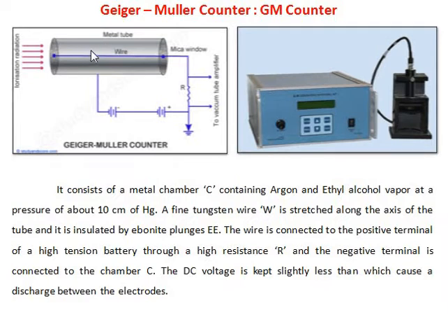The liberated electron interacts with other atoms. Further liberation of electrons takes place due to ionization. This process continues and a bunch of electrons appears. Since this tungsten wire is the anode, positively charged, and electrons are negatively charged, they are pulled towards the anode and swept out of the cylinder through this load resistance R, where it is amplified and counted as a pulse of electrons, which is equal to one beta particle. In this way it works.